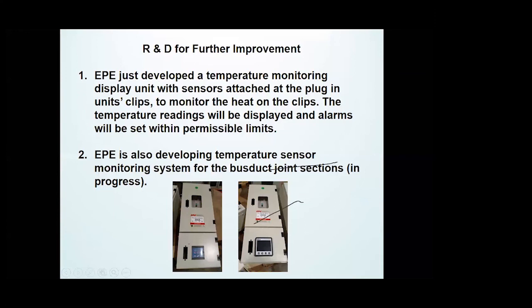As additional information from our R&D side, EPE has developed a temperature monitoring display unit with sensors attached at plug-in unit clips, to monitor the heat on the clip. The temperature reading will be displayed and alarms will be set within permissible limits. We are also currently developing a temperature sensor monitoring system for bus duct jointing sections. That's all from me — I hope you enjoyed the presentation.